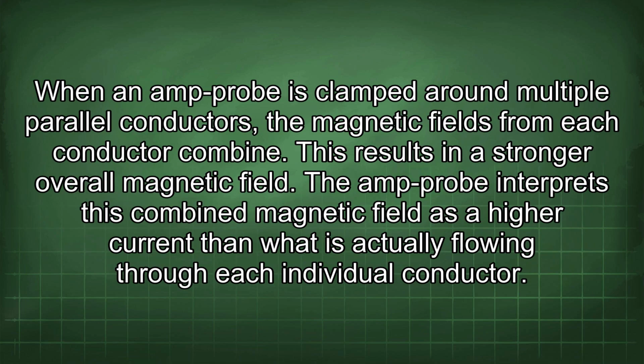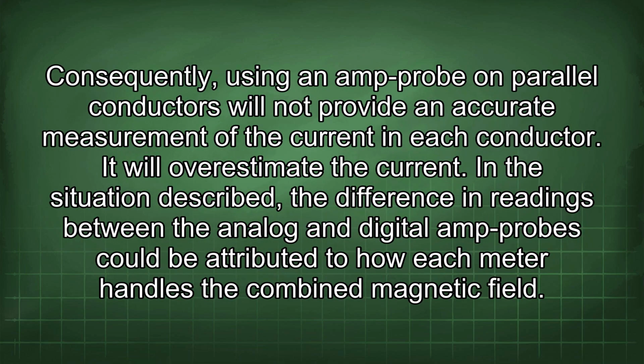When an amp probe is clamped around multiple parallel conductors, the magnetic fields from each conductor combine. This results in a stronger overall magnetic field. The amp probe interprets this combined magnetic field as a higher current than what is actually flowing through each individual conductor. Consequently, using an amp probe on parallel conductors will not provide an accurate measurement of the current in each conductor. It will overestimate the current.